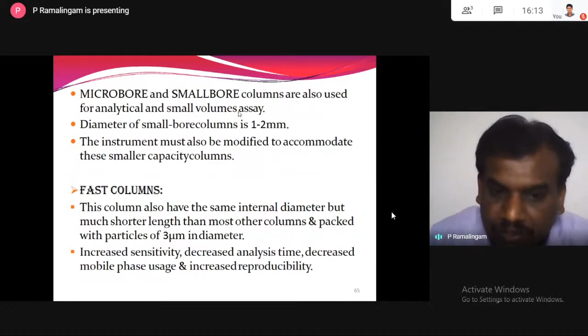To reduce your particles, see here, the conventional column is 25 centimeter, 5 micron. Now I want to convert this into a fast column. The 25 centimeter column becomes 10 centimeter, but the particle size should also be reduced from 5 micron to 3 micrometer. So this ultimately increases the sensitivity, decreases the analysis time, decreases the mobile phase use, and increases reproducibility.